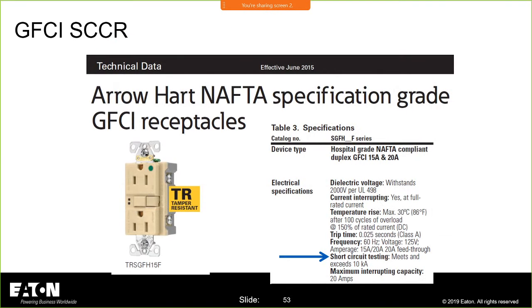Receptacles even have a short circuit current rating. You'll see down here it says a short circuit test meets and exceeds 10,000 amps. That's your withstand rating, because these devices are going to have to hold it together and supply that fault current to whatever has the fault downstream, whether it be an appliance plugged in or the conductors connected to the load terminations of this GFCI receptacle. The contacts and the electronics inside are going to have to hold it together while that fault current passes through it.